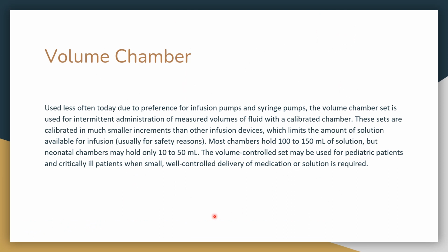Volume chamber. Used less often today due to preference for infusion pumps and syringe pumps. The volume chamber is used for intermittent administration of measured volumes of fluid with a calibrated chamber. These sets are calibrated in much smaller increments than other infusion devices, which limits the amount of solution available for infusion, usually for safety reasons. Most chambers hold 100 to 150 mLs of solution, but neonatal chambers may only hold 10 to 50. The volume-controlled set may be used for pediatric patients and critically ill patients when small, well-controlled delivery of medications or solutions is required. Don't usually use these anymore.